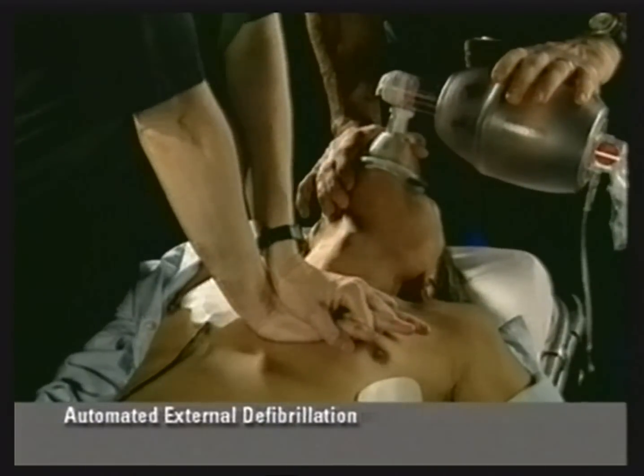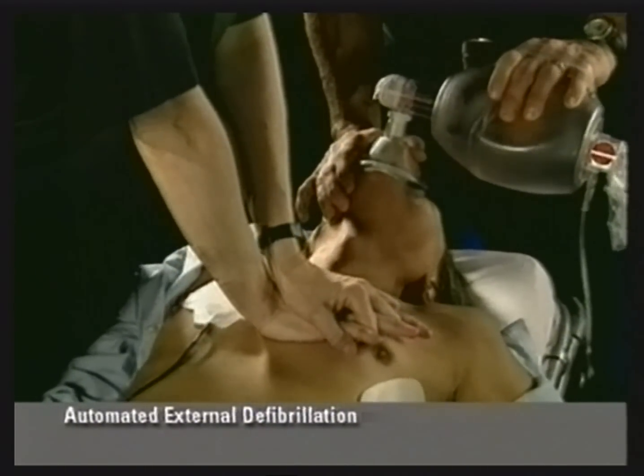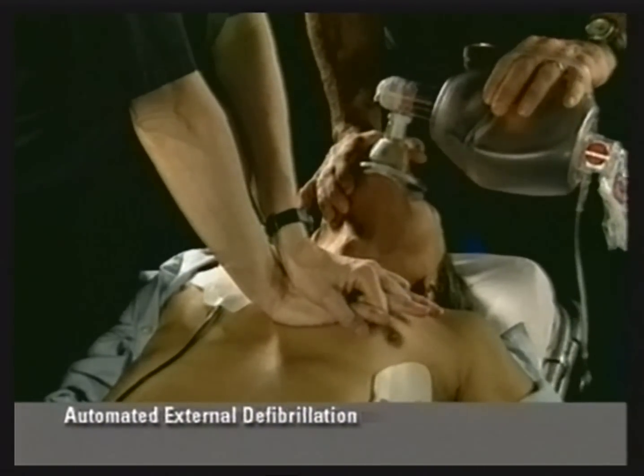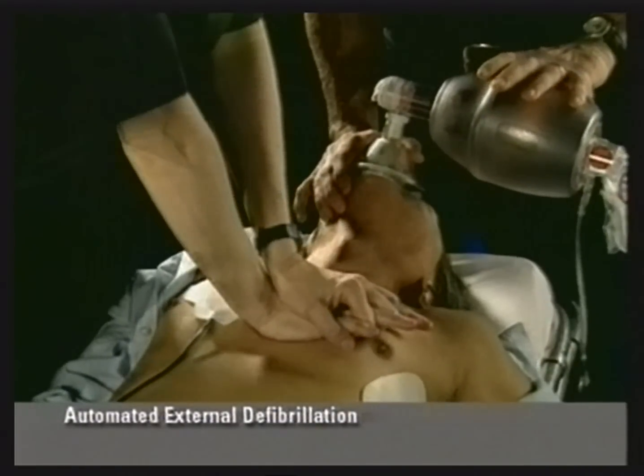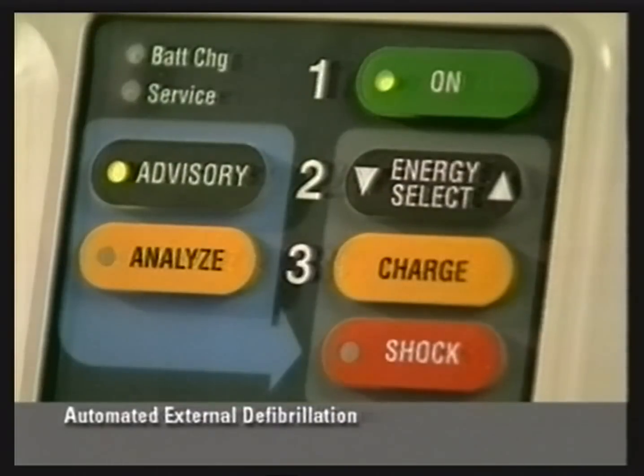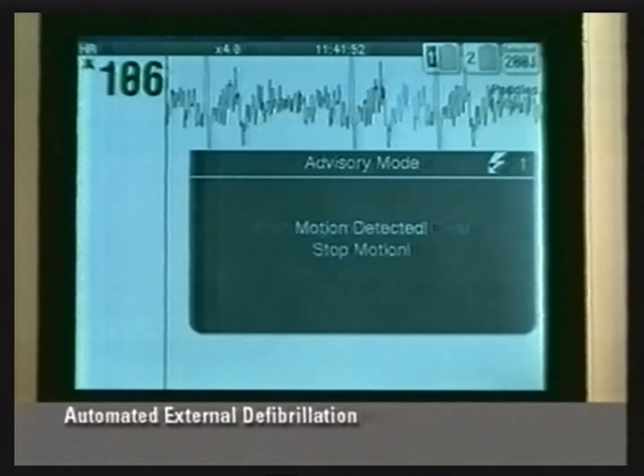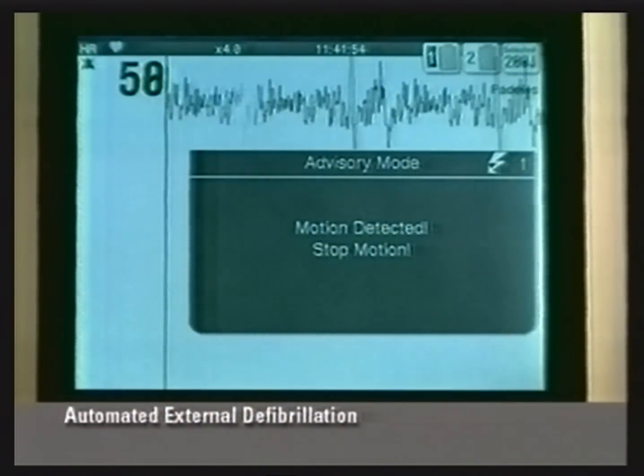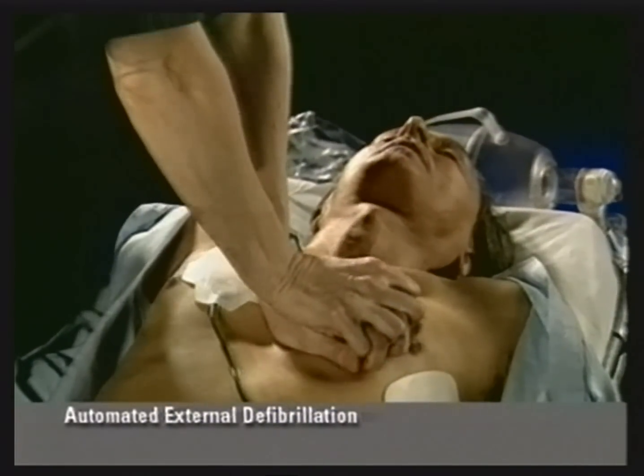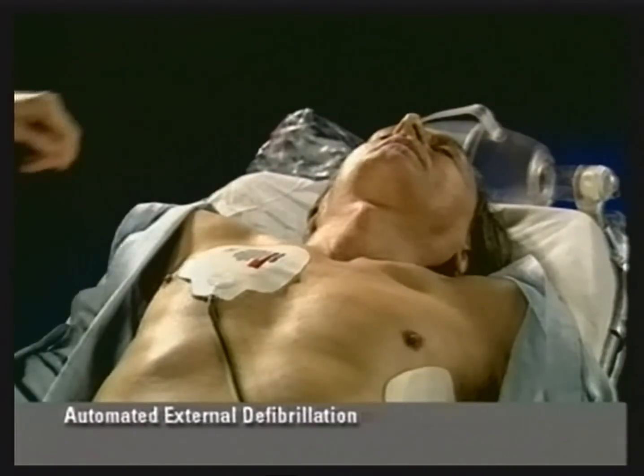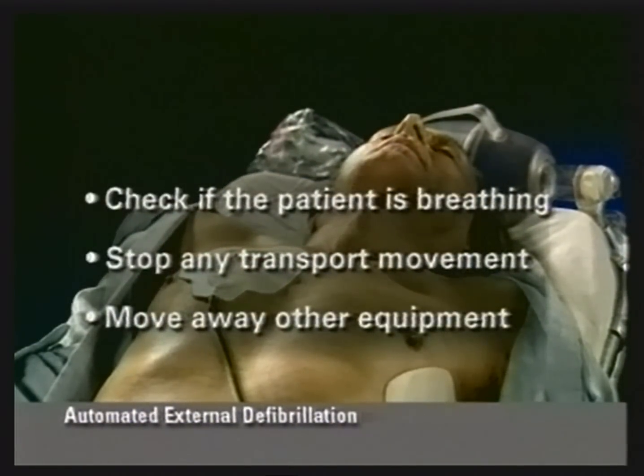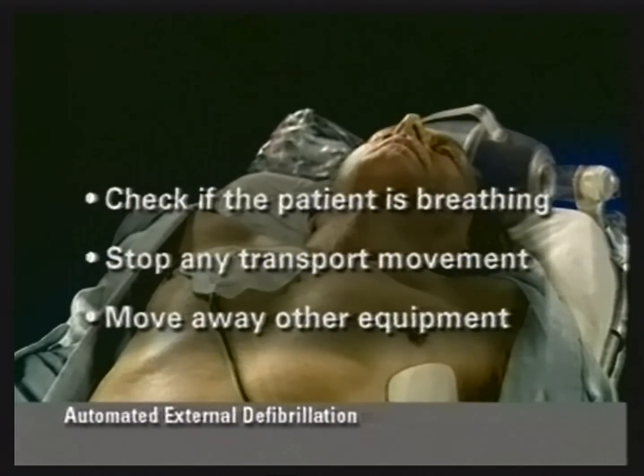Motion detection is a Physio-Control patented feature designed to prevent analysis of ECG artifact and to prevent a rescuer from receiving a shock. If motion is detected during ECG analysis, you see and hear, "Motion detected. Stop motion." You need to stop touching the patient, stop CPR, cardiac compression, and manual breathing. Check for other possible causes of interference if present, and stop any transport movement. Move away handheld communication devices or other equipment that may emit interfering radio frequency signals.